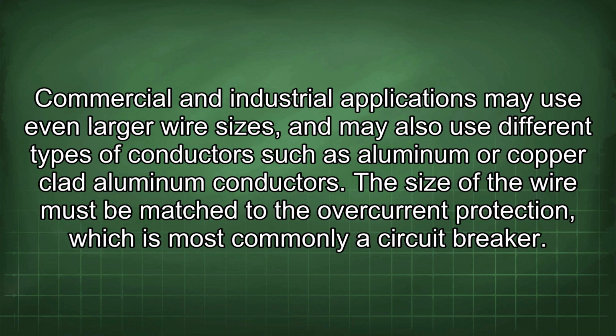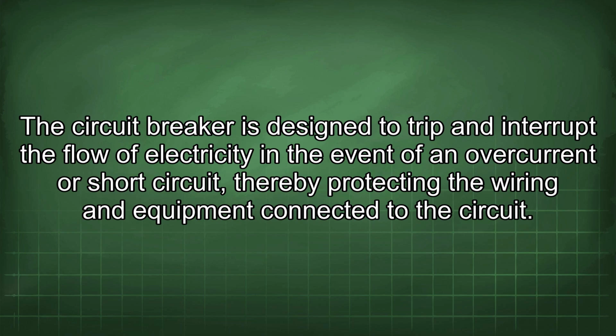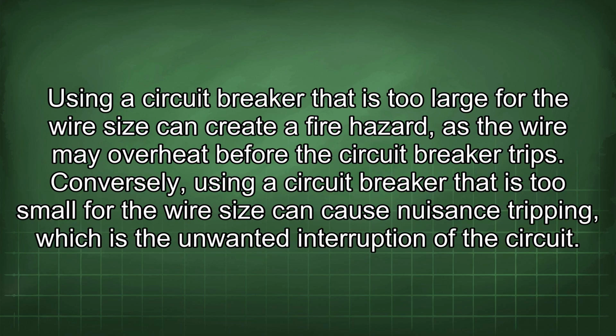Commercial and industrial applications may use even larger wire sizes and may also use different types of conductors such as aluminum or copper-clad aluminum conductors. The size of the wire must be matched to the overcurrent protection, which is most commonly a circuit breaker. The circuit breaker is designed to trip and interrupt the flow of electricity in the event of an overcurrent or short circuit, thereby protecting the wiring and equipment connected to the circuit. Using a circuit breaker that is too large for the wire size can create a fire hazard, as the wire may overheat before the circuit breaker trips.